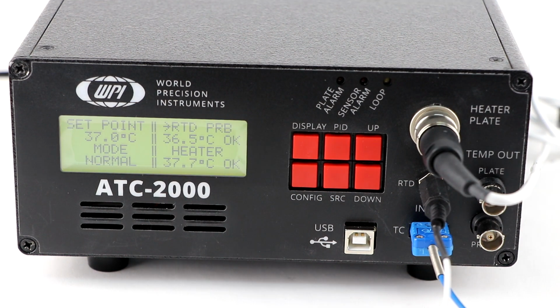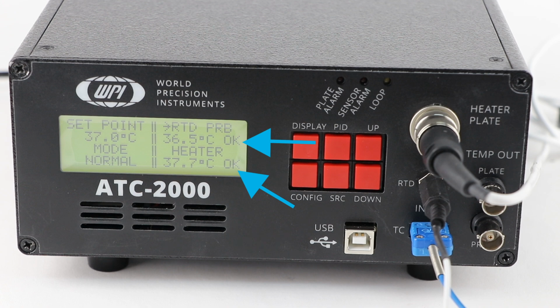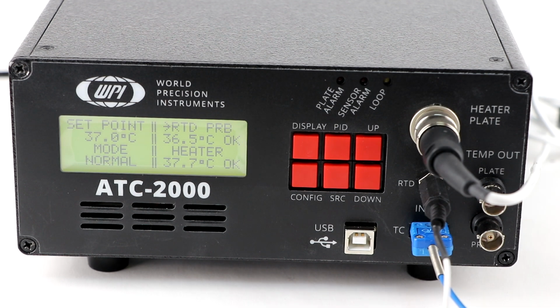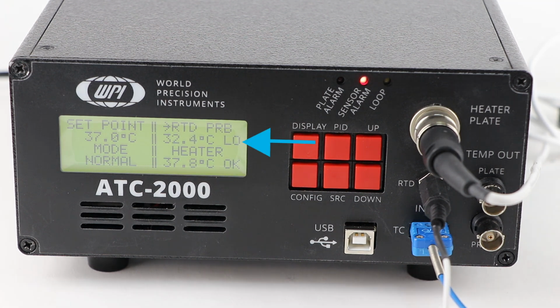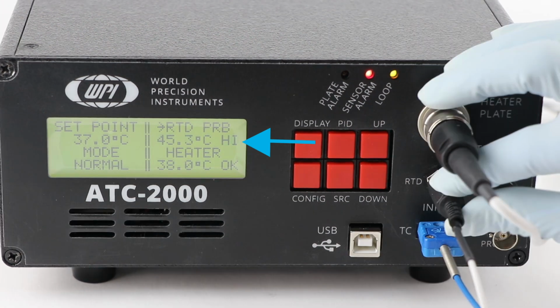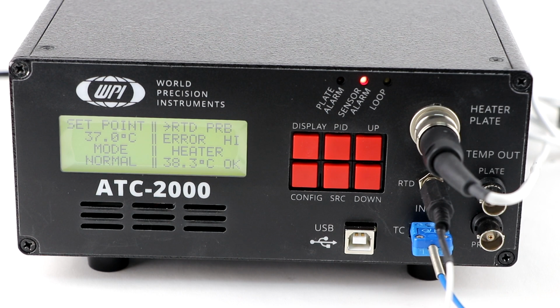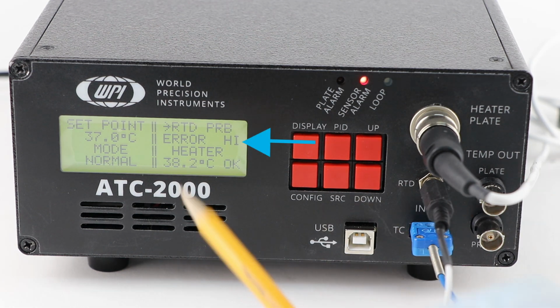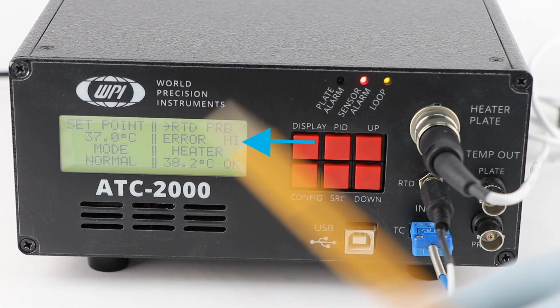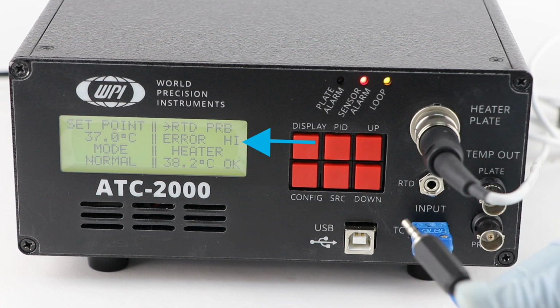The OK next to the temperature here indicates that the temperature falls within the parameters defined by the low and high alarm limits. If the temperature falls below the low limit, low displays instead of OK. Likewise, if it exceeds the high limit, high displays. If the message error high appears on the temperature display, the temperature probe is either disconnected or defective.